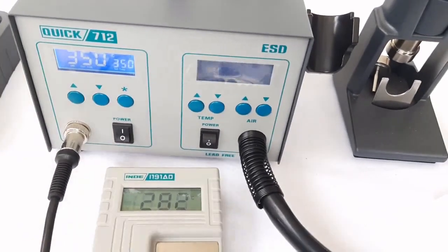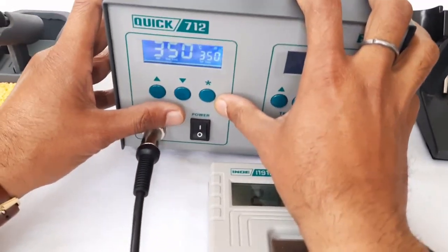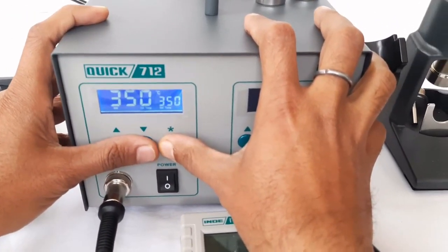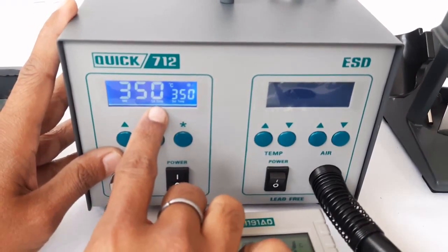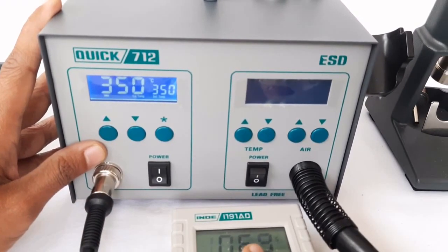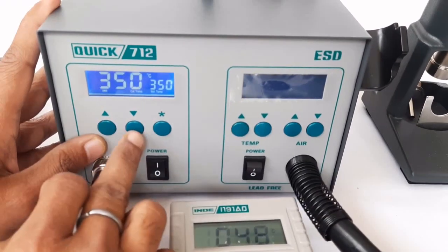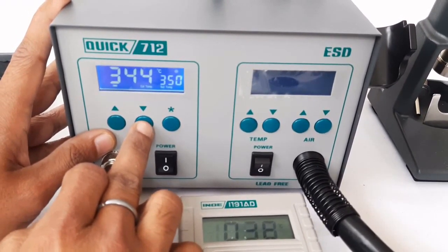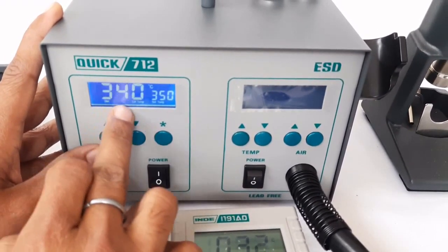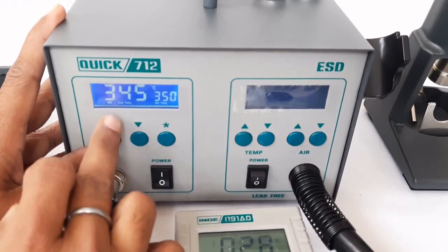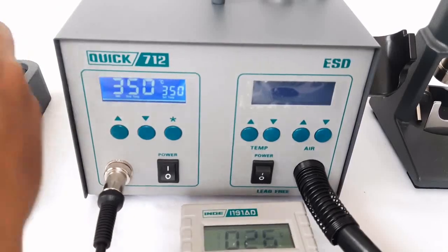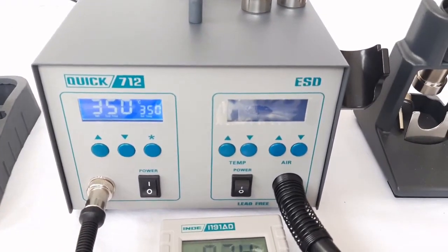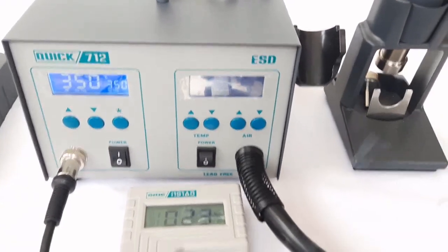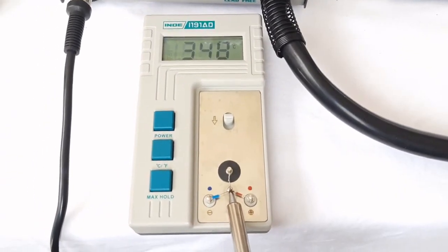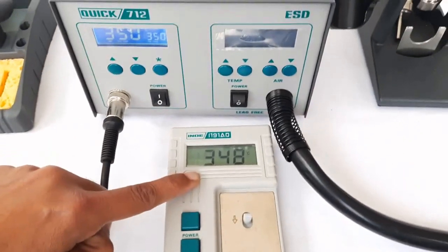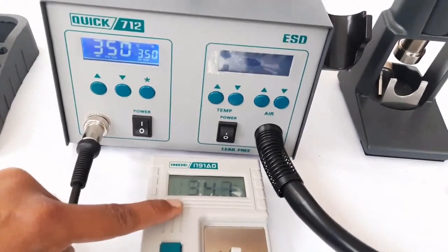We will calibrate this unit, and we will show you how it is calibrated. First, we need to press this star button and press this up and down button, and now it is entered into the calibration mode. We need to enter the exact value which we have observed on the calibrator, that was 340 degree. By using the down button, we can achieve that value 340. Then again press the star button. Then the calibration is working right now, and we will verify whether the value which we have entered has been accepted by the controller, and we will check the actual temperature once again. See, the set temperature is 350 and actual temperature is close to 350. So unit is now calibrated and within the tolerance limit.